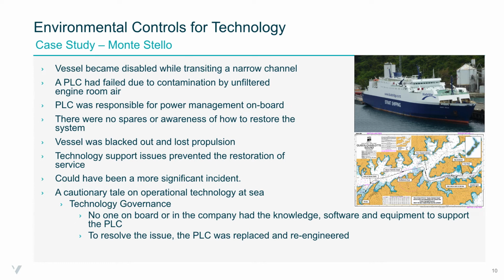The PLC itself was not able to be recovered to full operation, and the vessel had to return to port. The upshot of the investigation was that there was a contaminated supply of air from the engine room, and for a significant period there'd been no maintenance of the filters, and contaminated oil particles had found their way into the enclosure that controlled the PLC processor board, contaminating it. In that situation, it's quite difficult to determine the exact cause of failure, but it's thought the oil deposited on the processor board had led to a breakdown of the board's ability to transfer its heat out to the cooling system.